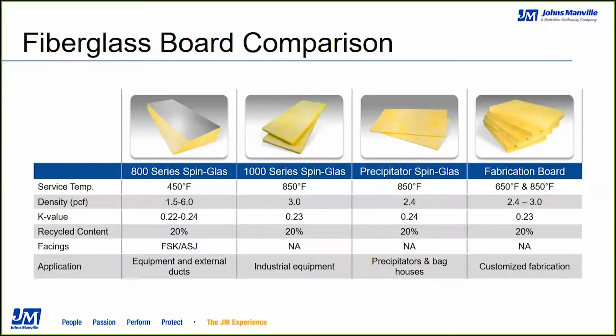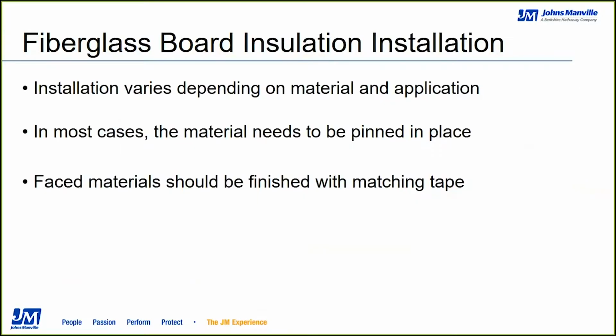The precipitator spin glass is a semi-rigid, slightly flexible industrial equipment insulation. And ultimately, fabrication board, available in both 650 and 850 degree options, is intended for custom fabrication of pipe and tank wrap. Ultimately, the installation varies depending on the material and the application. As mentioned, the material will likely need to be pinned in place if attaching it to ductwork, and then can be finished off with corresponding tapes.